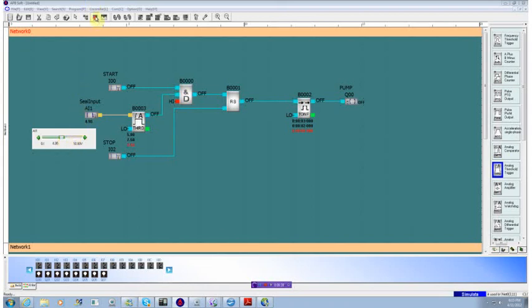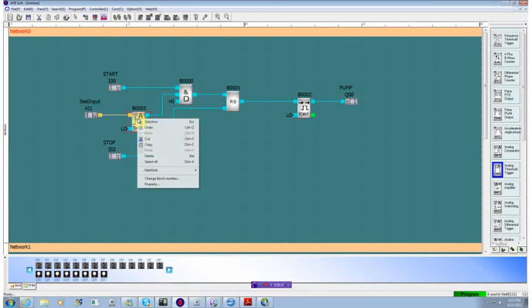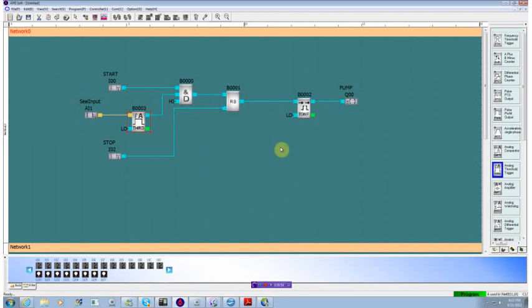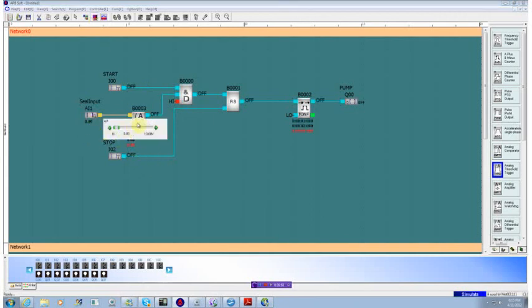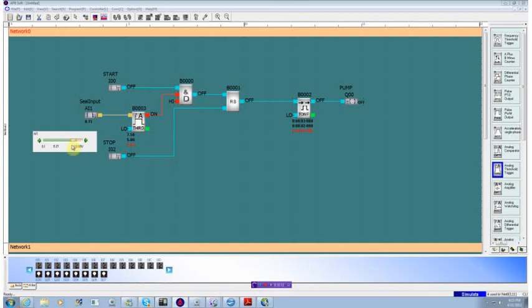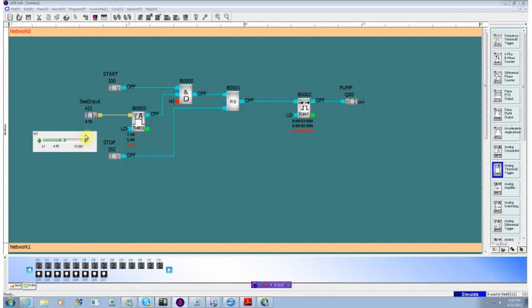Let's stop this and go back to these properties. Let's set this one to 7.5. So it's going to turn on when it hits 7.5. And we'll set this to 5, which means it turns off when it drops below 5. Running our simulator again, activating our input. We see that when we hit 5, nothing happens. When we hit 7.5, it turns on. We can continue all the way up to 10. And then as we bring it back down again, once we hit 5, it turns it off again. So this gives us an input with hysteresis. The nominal value of on is 7.5. But if we get some noise on the line, it won't actually trip it off until it drops below 5.